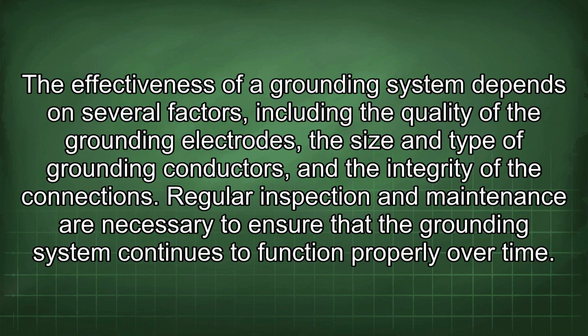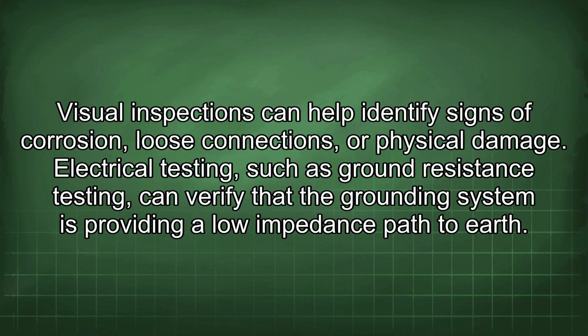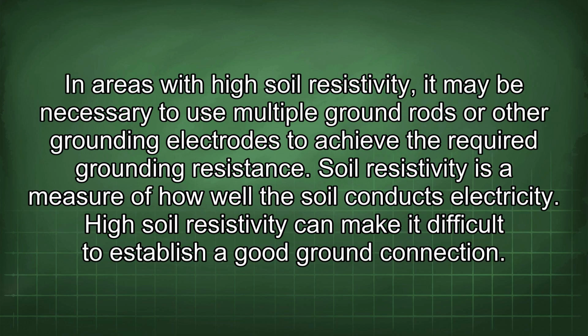The effectiveness of a grounding system depends on several factors, including the quality of the grounding electrodes, the size and type of grounding conductors, and the integrity of the connections. Regular inspection and maintenance are necessary to ensure that the grounding system continues to function properly over time. Visual inspections can help identify signs of corrosion, loose connections, or physical damage. Electrical testing, such as ground resistance testing, can verify that the grounding system is providing a low impedance path to earth. In areas with high soil resistivity, it may be necessary to use multiple ground rods or other grounding electrodes to achieve the required grounding resistance.